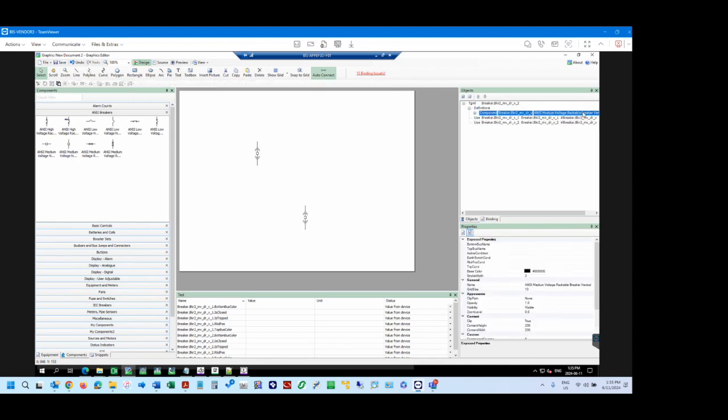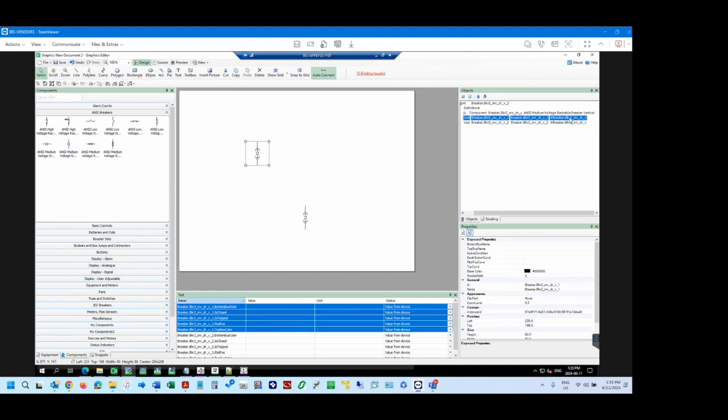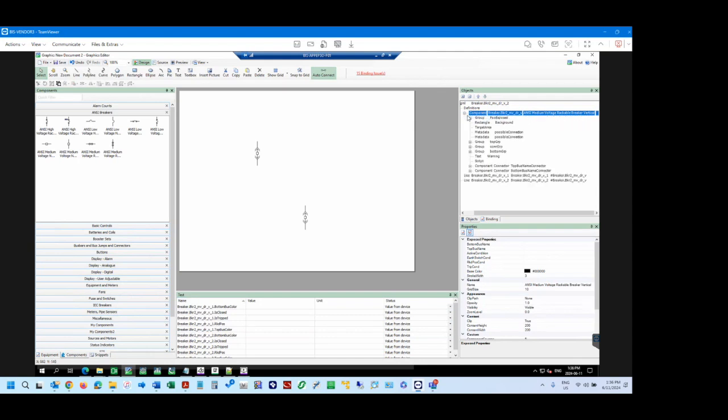That level is basically defining breaker.bkr2 MV, so medium breaker draw out, rackable, and vertical underscore V. And you can see the hashtag at the end of the breaker name here. That is your reference to what definition it is. If I modify this definition, there's a whole bunch of stuff I can tweak, and if I do that at the definition level, it will change both of those breakers all at once, like the properties of those breakers.